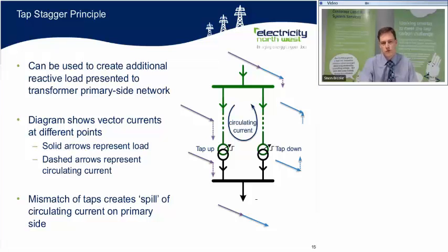And then as we move up through the diagram, we see those purple and blue vectors repeated through each transformer, with the solid lines indicating the load current through each transformer. And we also see a dashed line in opposite directions for each transformer. And this represents circulating current around the transformer. So if we tap up the transformer on the left and we tap down the transformer on the right, we will create a circulating current around those transformers, which is represented with those dashed vectors.